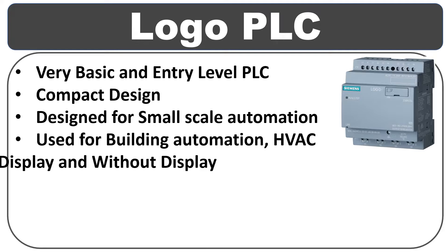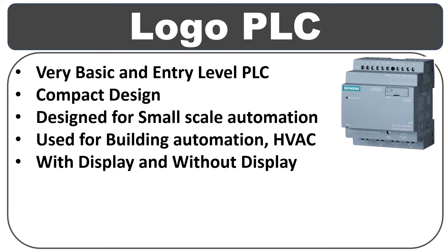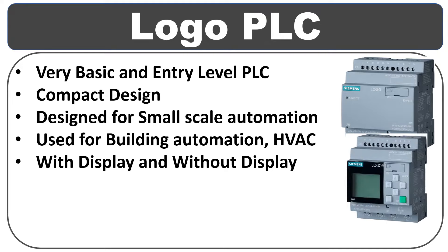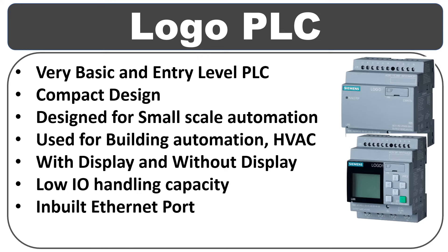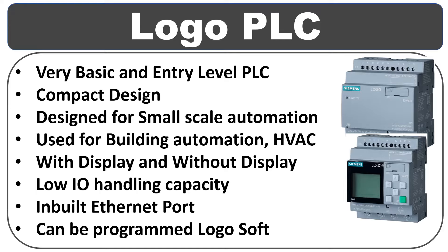The Logo PLC comes in two versions: with display and without display. Its I/O handling capacity is very low. It has onboard DI — that is 8 DI and 4 DO — which can be extended further. The Logo PLC has an inbuilt Ethernet communication port and can be programmed using the Logosoft program.